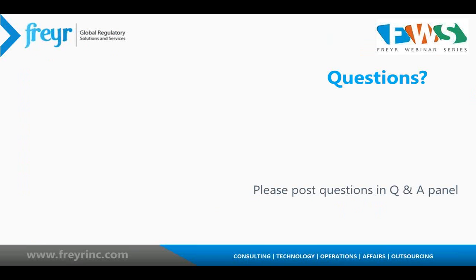We'll complete the submission of all the different possible test scenarios as required by the FDA via the ESG gateway. That's the FDA electronic gateway, on behalf of the client. And then finally, once they pass those test case scenarios, Freyr will request activation of a production GUDID account. And from that point forward, the labeler can now start publishing production DI, device information, to the GUDID. Hopefully that addressed that one.